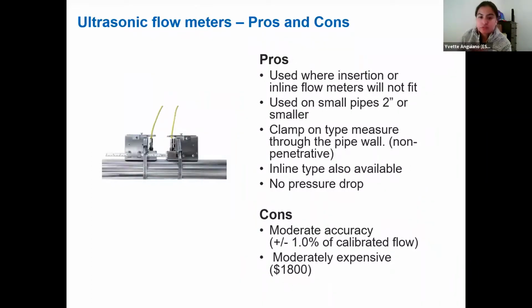So if you're in the predicament that you don't have pipe that you can cut into or penetrate, and you're looking for a flow meter that doesn't do that, you can use this ultrasonic flow meter. They tend to be used on smaller pipes or pipes that you can't cut into. Some are clamp-on style, and they have inline versions available. These send an ultrasonic wave to measure the water flow, and they're moderately accurate and moderately expensive.